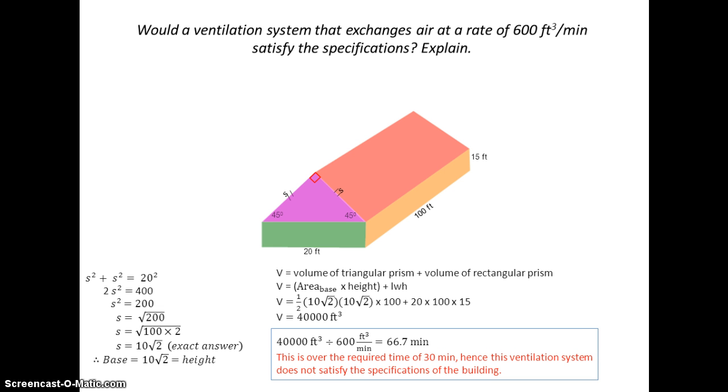If I divide that by 600 cubic feet per minute, I can see that it's going to take much too long, way over 30 minutes for this ventilation system to exchange all the air. So it's not adequate.